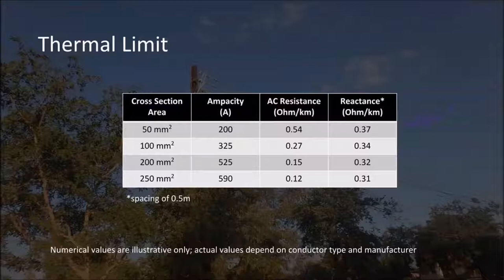On the slide you see now is an example of how we'd actually go about selecting the conductor. We would pick one that meets the thermal limit so it doesn't overheat, as well as one that is large enough that we don't have a voltage drop issue.